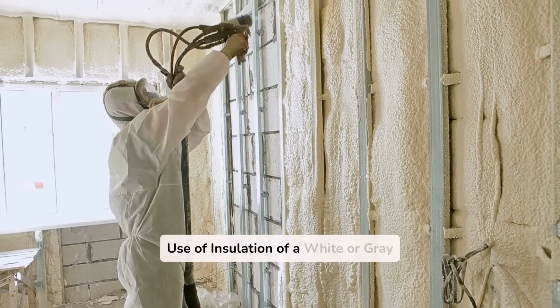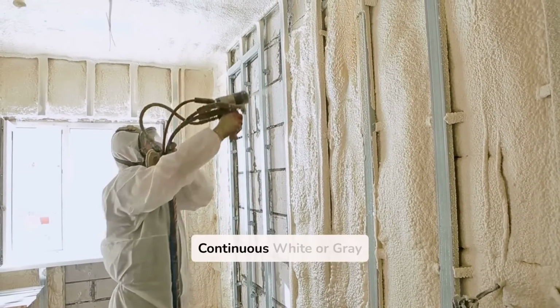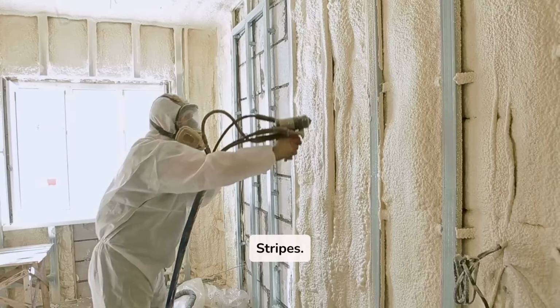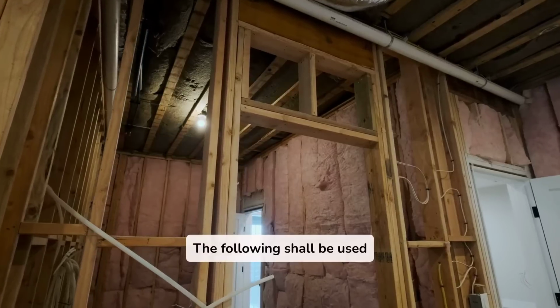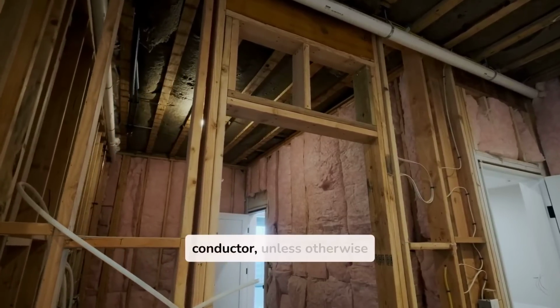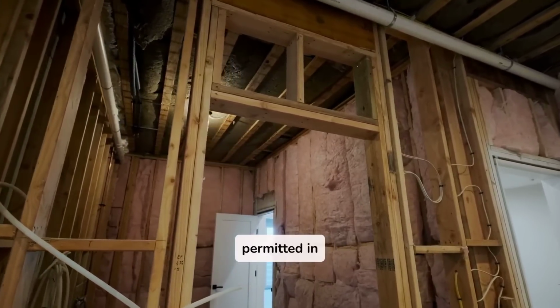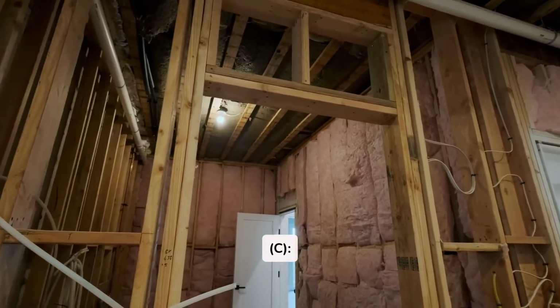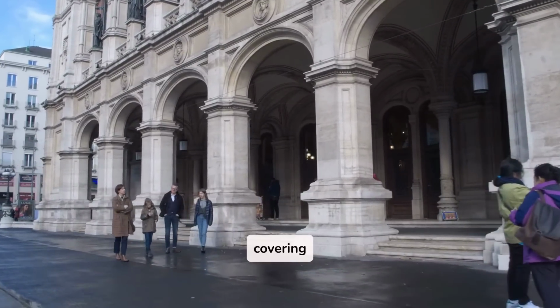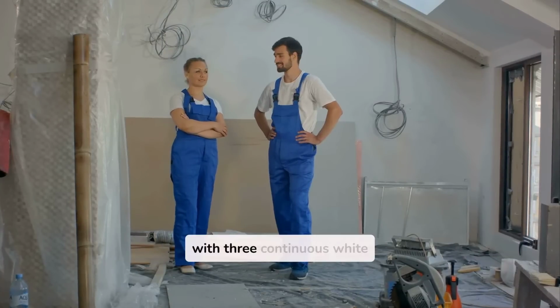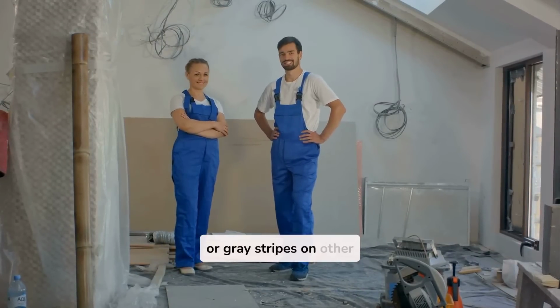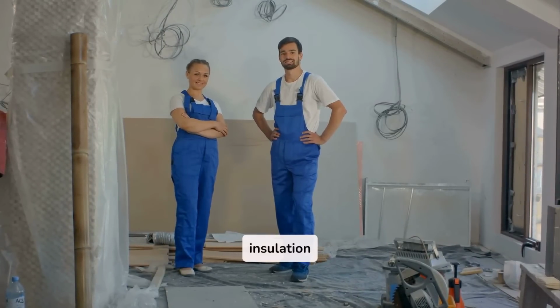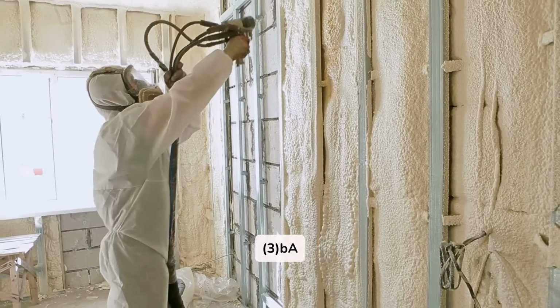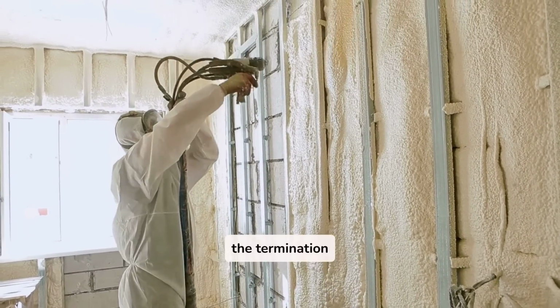200.7 Use of insulation of a white or gray color, or with three continuous white or gray stripes. A. General. The following shall be used only for the grounded circuit conductor, unless otherwise permitted in 200.7 B and C. 1. A conductor with continuous white or gray covering. 2. A conductor with three continuous white or gray stripes on other than green insulation. 3. A marking of white or gray color at the termination.